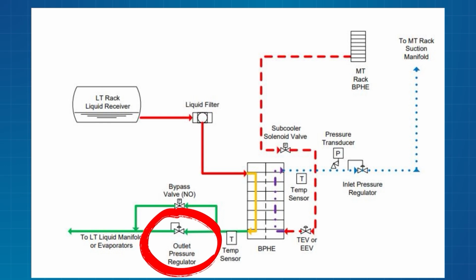If I'm sending out 50-degree liquid at 138 PSI, my 1.5 ton valve is gonna have the same offset factors. They're about 1.5, and we will cover that. About 1.5 times, right? They're gonna cancel each other out. My 1.5 ton valve is gonna be pretty close to 1.5 tons. All right? Now, here's where things can go wrong. My subcooler goes down. Now I've lost efficiency out of this side, and I'm not getting it back on the subcooling side. I've just lost efficiency.